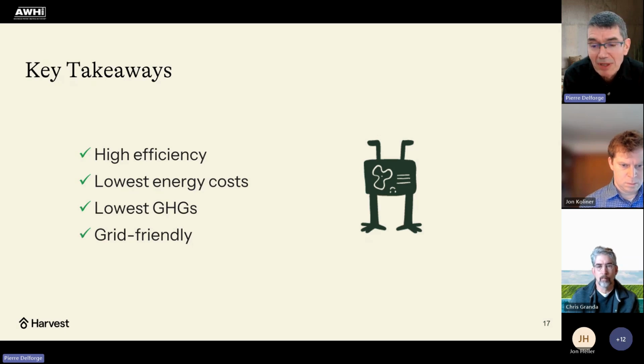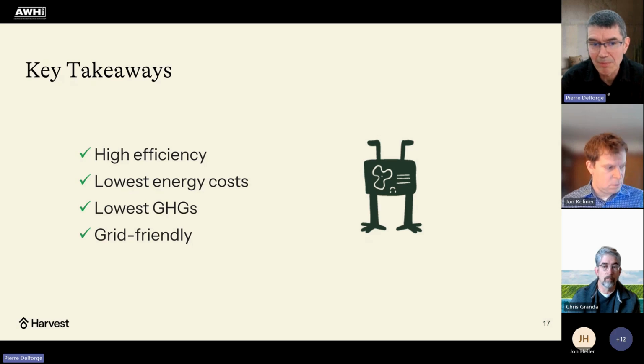To be honest, we will see lower efficiencies as temperatures drop near zero — first you get more defrost operation, and then sometimes backup, because if temperatures drop below zero the capacity of the Sanco 2 reduces and we need backup heat. The way we do backup — I haven't mentioned this — we use a tankless electric water heater on the hydronic side, and the Sanco 2 continues to operate. It's not a switch from the heat pump to electric resistance; it's a variable capacity electric resistance supplement to the Sanco 2 to meet the heating load. So it's still very efficient, but the more electric resistance you use, the lower your COP is going to be.